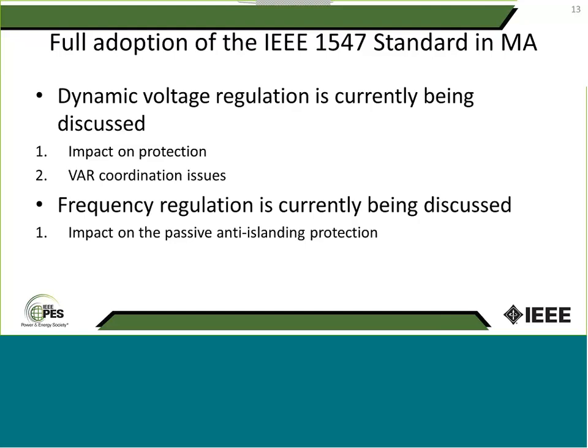One of the issues is impact on system protection, and we're still trying to understand it. When it comes to enabling voltage regulation, is this reactive power component going to impact the fault current? Most faults on the power system are like sink VARs. So how is that going to work with volt-VAR enabled or constant power factor mode enabled on the DER itself? Plus there are VAR coordination issues. This is a really serious issue. If you just enable volt-VAR with no coordination amongst inverters or DERs in general, these functions can do more harm than good to your distribution system.